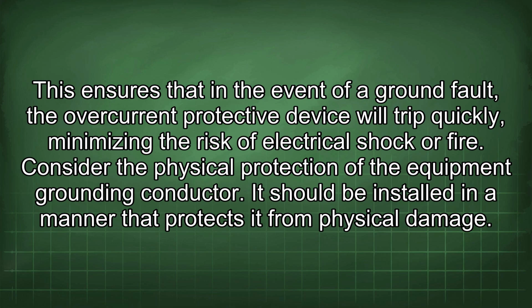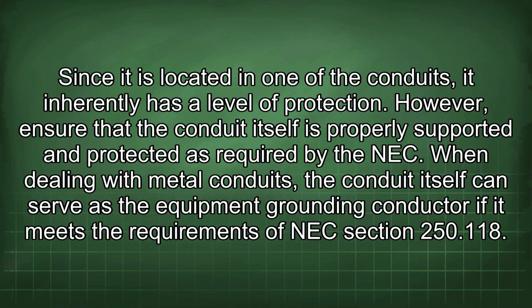Consider the physical protection of the equipment grounding conductor. It should be installed in a manner that protects it from physical damage. Since it is located in one of the conduits, it inherently has a level of protection. However, ensure that the conduit itself is properly supported and protected as required by the NEC.